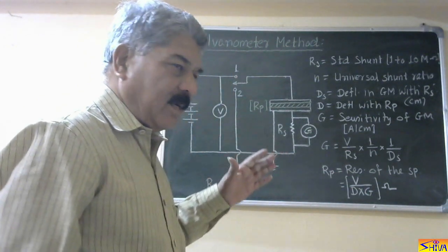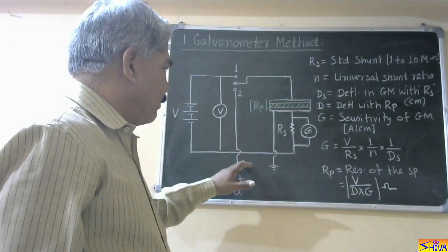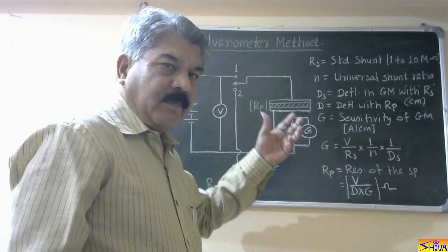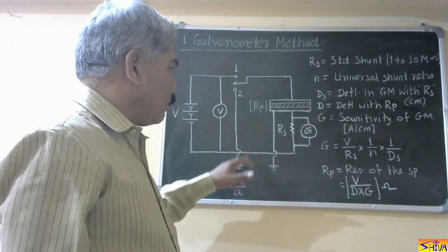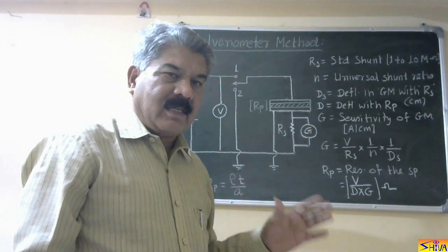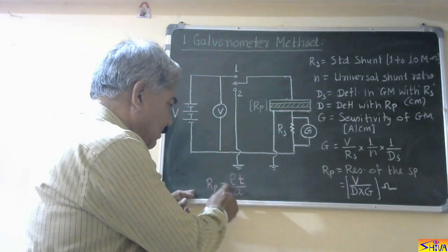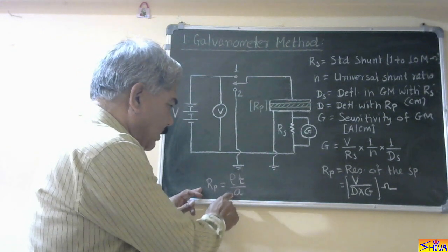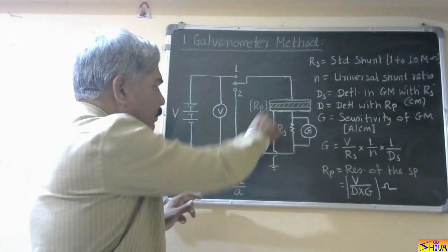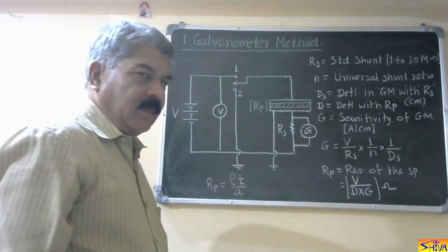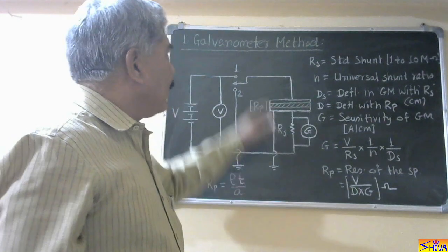After the test is complete, we connect to ground so that any residual charges are discharged. As a precautionary safety measure, we discharge the test sample so that residual charge does not harm operating personnel. If we want to find volume resistivity rho, then Rp equals rho times t upon A, where t is the thickness of the sample and A is the area. In this way, we determine the insulation resistance or DC resistivity by the galvanometer method.